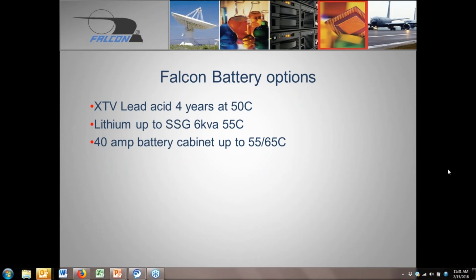So that's the kind of runtime and life we're seeing. Depending on customer needs, it comes down to that. People ask about lithium all the time because they want less rack space, which is expensive, or they have a weight issue and need less weight, or an application with a lot of possible discharges. With lithium you get 2,000 discharges over the life versus 500 discharges with lead acid. That's what we see around lithium.